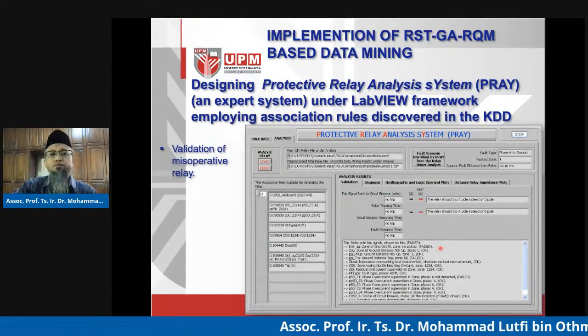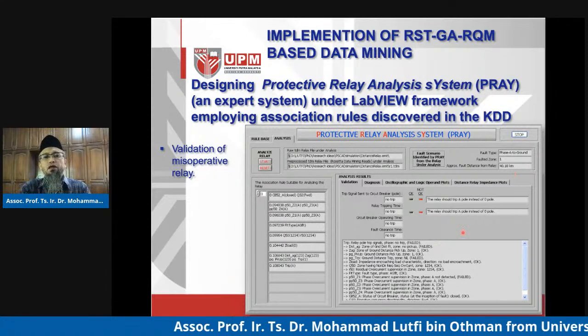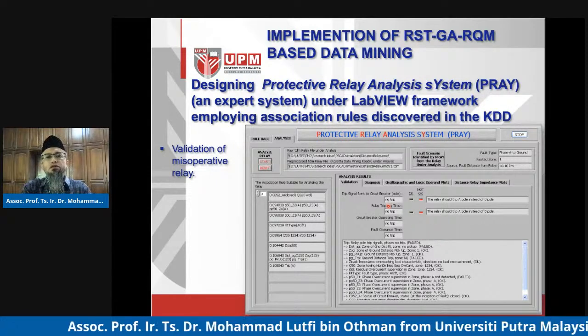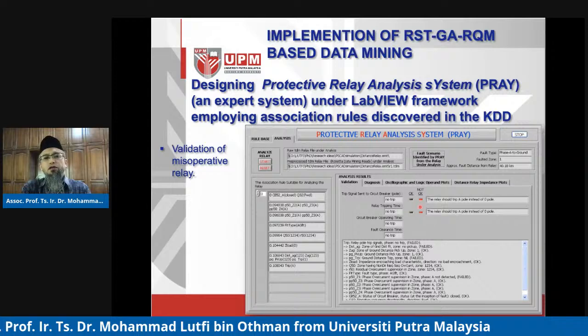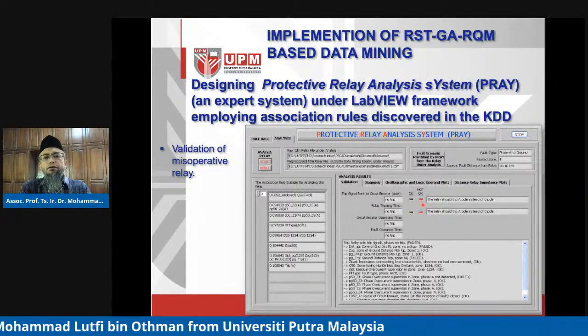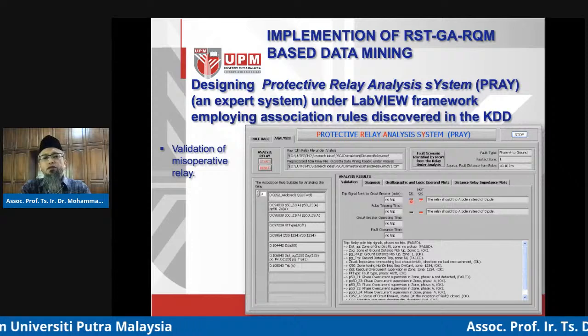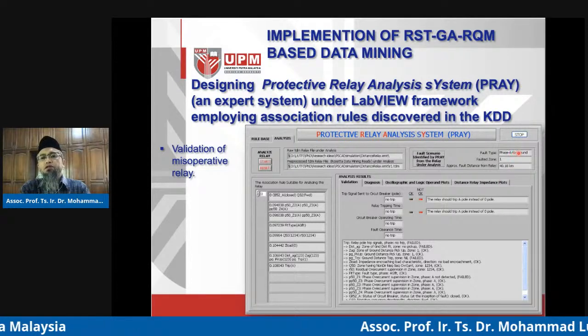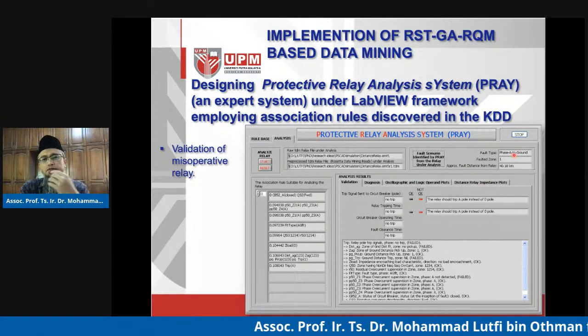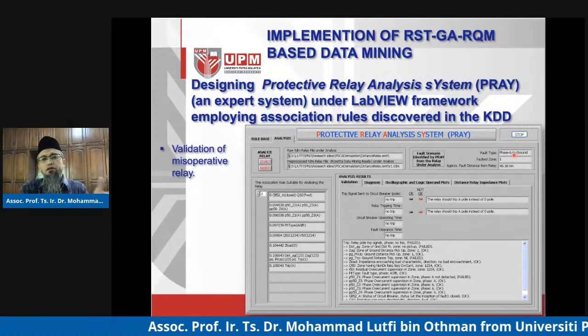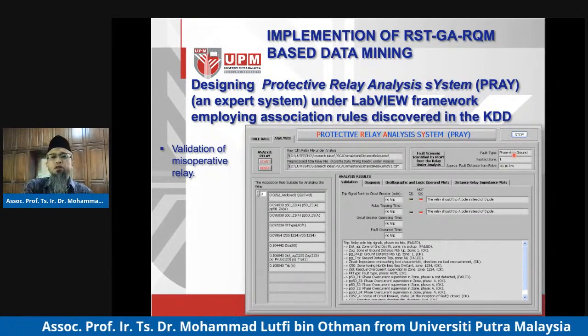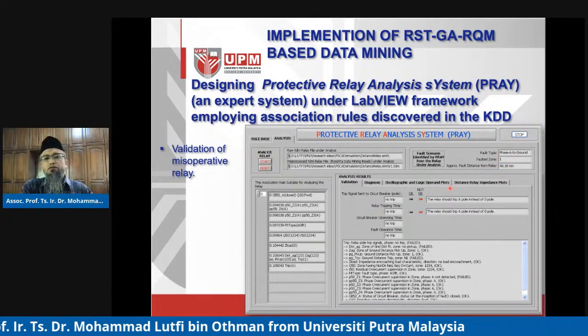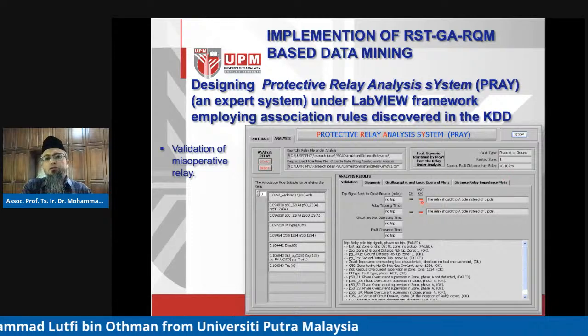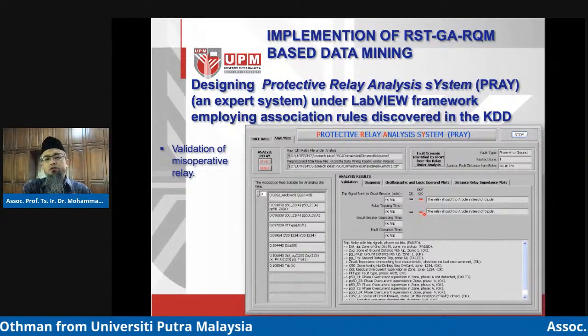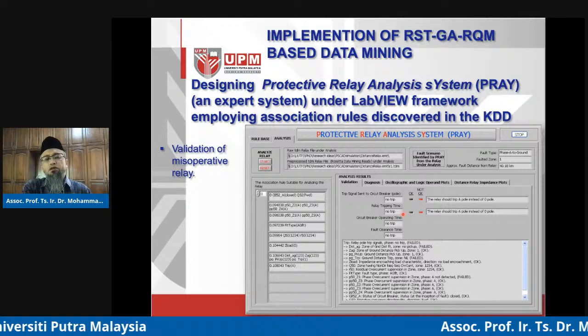So what about the unhealthy relay, a failed relay? Of course, it has been confirmed that no tripping has occurred, even though the fault has been detected. Again, this fault is actually detected out of the data within the relay itself, the measured impedance within the relay itself, the model relay in this sense. So the relay has failed to operate, and of course no timing is recorded.